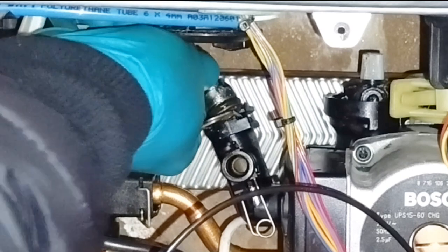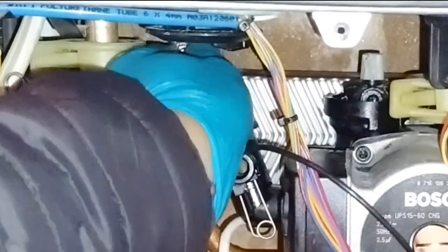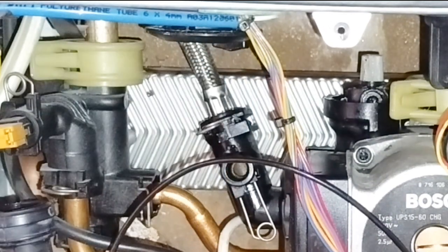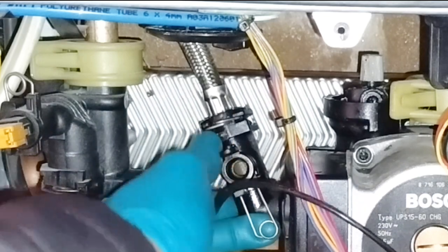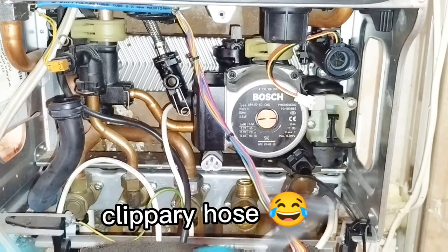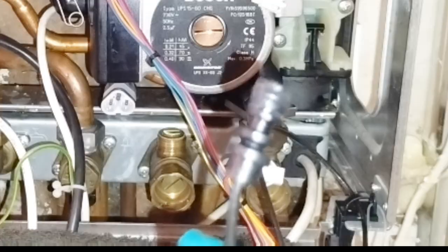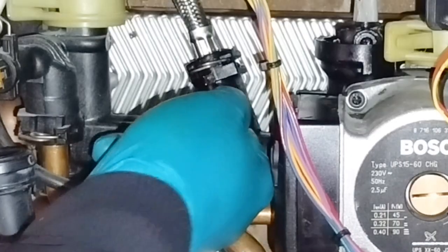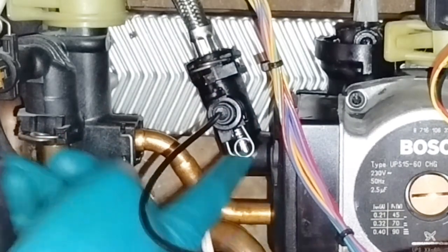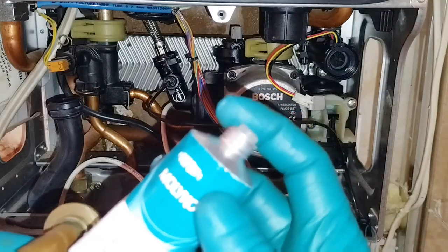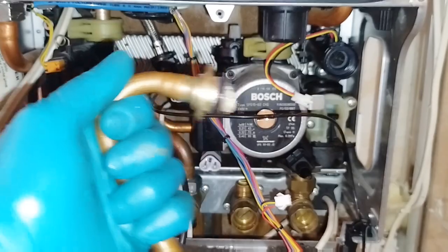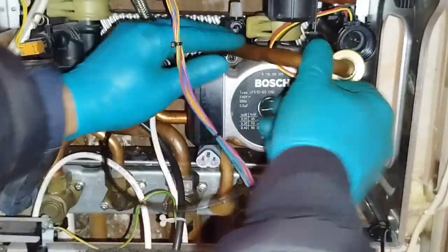Now, because we had it lubricated, the expansion vessel's hose has gone in nicely. We put the clip back in, and now the clip capillary hose for the pressure gauge goes in nice and easy. Clip goes back in, even more silicone grease. This time it goes onto the pipe, the cold feed pipe, which will sit here in front of the flow turbine.